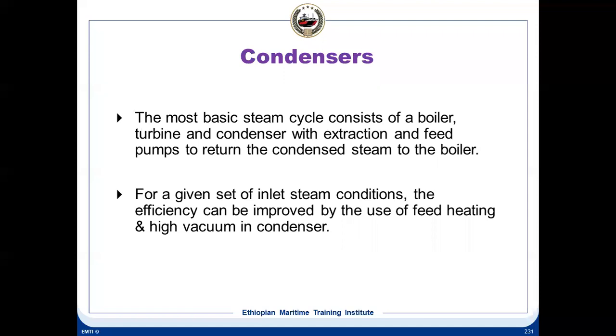The steam cannot be put back into the boiler straight away. It has to be condensed into water so that it can be handled properly. Whatever additives we are required to put, we put all that, and then it is sent back to the boiler. So for that purpose, it is cooled down, normally with seawater, or if you have a HT-LT system, the LT will cool down the steam in the condenser.